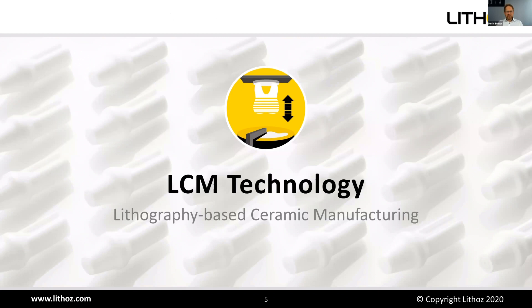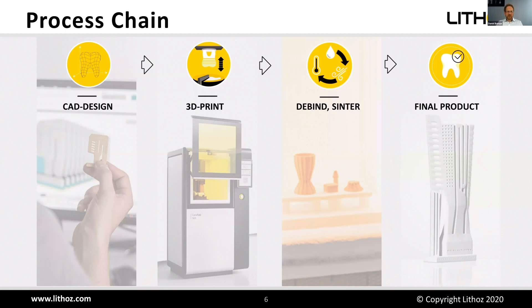What about the LCM technology? LCM stands for lithography-based ceramic manufacturing, a 3D printing technology for all kinds of ceramic materials. The process chain comprises a designing step — scanned from a patient or designed in CAD software — always ending in STL format, which gets transferred to the printer. The 3D print is conducted, producing a so-called green body, which is a composite of ceramic material and photopolymer used as binder. We then do thermal post-processing, of which debinding and sintering are parts. Debinding means burning out the binder, and sintering is the consolidation of ceramic particles until we reach the final product.